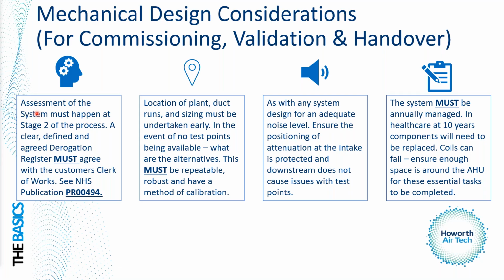But when we're going into existing hospitals and putting in an operating theatre, we may have constraints from very old designs of the building, and obviously that then has to go into a derogation. To get a derogation through is very complex, and it goes all the way through the NHS up to the chief executive. There's very in-depth guidance in this document here, which is what my colleague told me to quote and reference. So if anybody is on the call today and they get involved with derogations or early stages of design, then just take a note of that, go away from the webinar, and download that document. There's a lot more detail in that than there is in this presentation on derogations, but it's something that you need to be aware of.